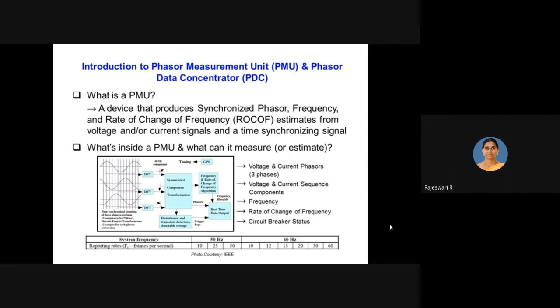So where can these PMUs be integrated in the power system measurement infrastructure? The point at which we need this kind of measurement is especially at a bus, that is a substation. Substations with higher voltage ratings are all being equipped with this PMU, where the CT/PT output is fed to the PMU. This CT/PT output is nothing but analog signal, voltage and current signal, and this PMU has a link with the GPS system.